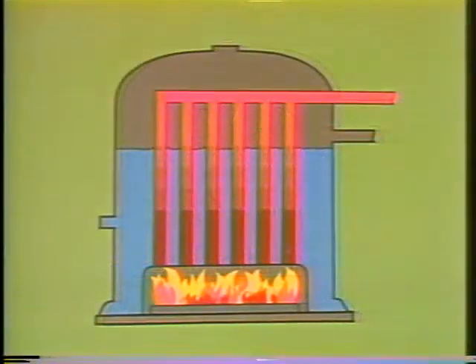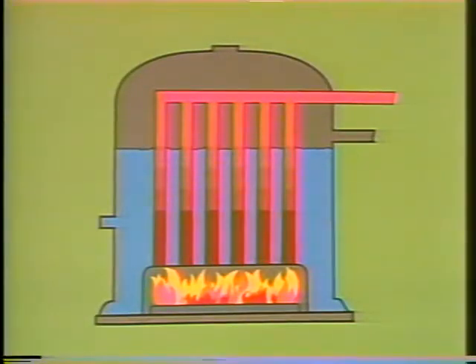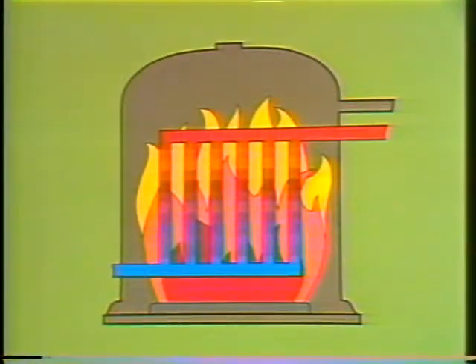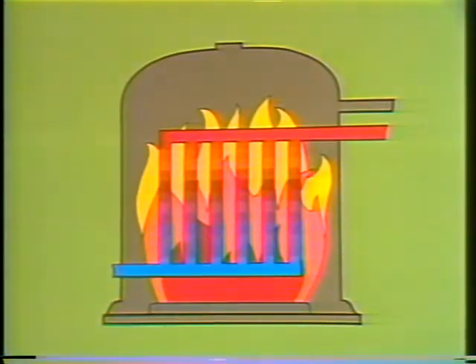Fire tube boilers produce steam by operating at low pressure with large volumes of water in the boiler, which allows for more stable operation. Water tube boilers, on the other hand, have less water and are more responsive to changing steam demands. In addition, they are capable of producing the high-pressure, high-temperature steam needed for efficient operation. Since it's the water tube boiler that you're most likely to see at your plant, let's take a closer look at it.